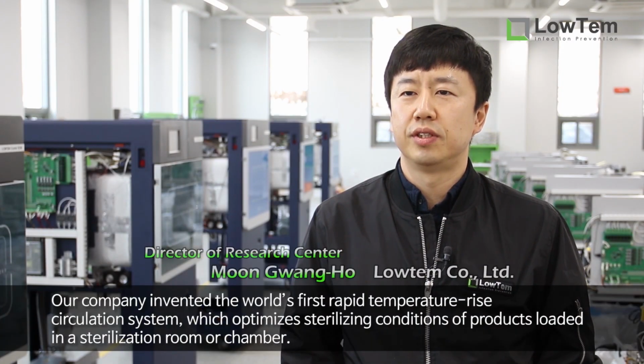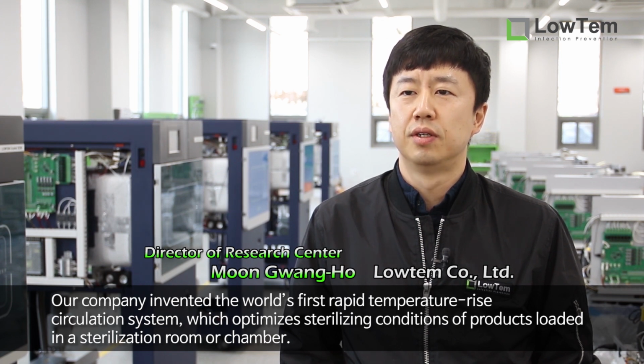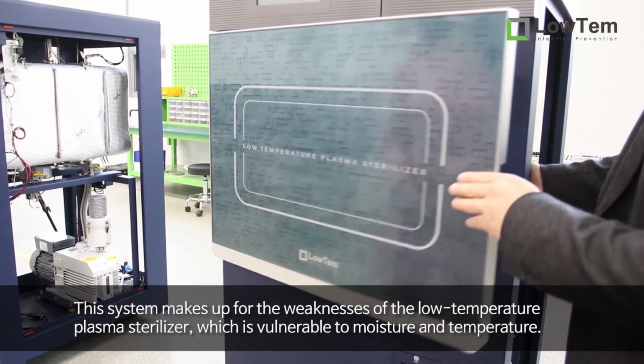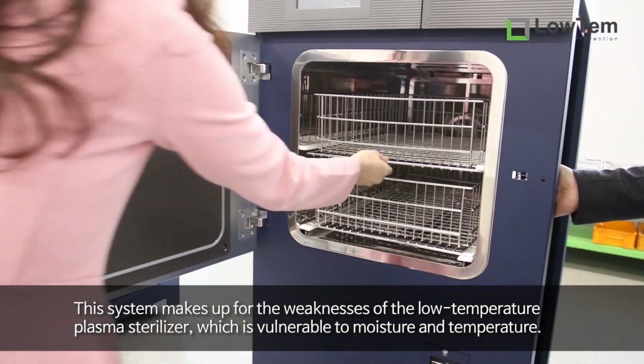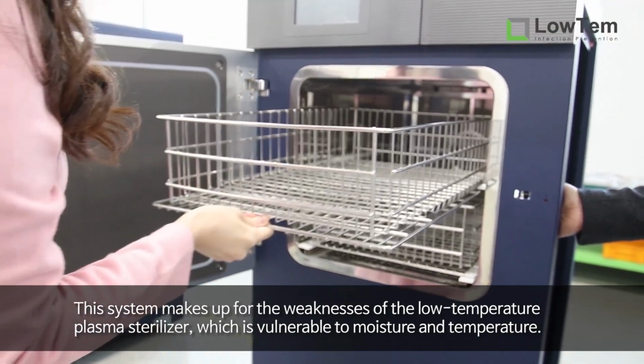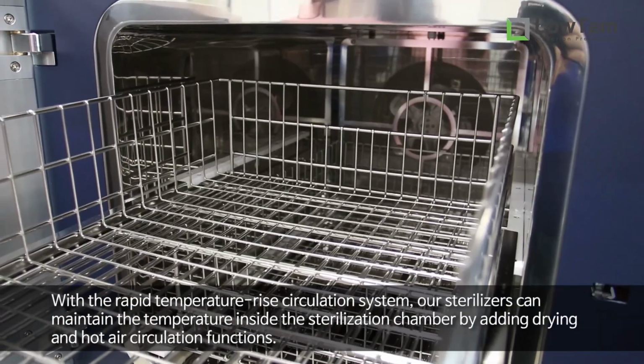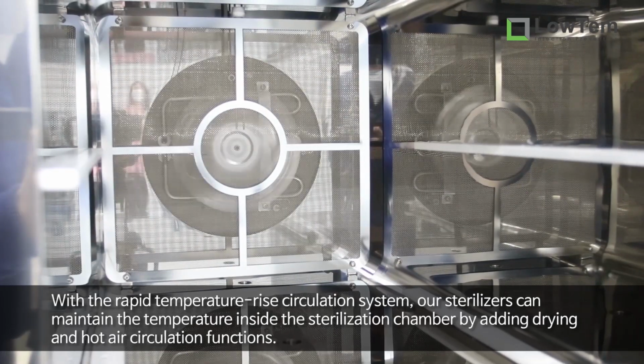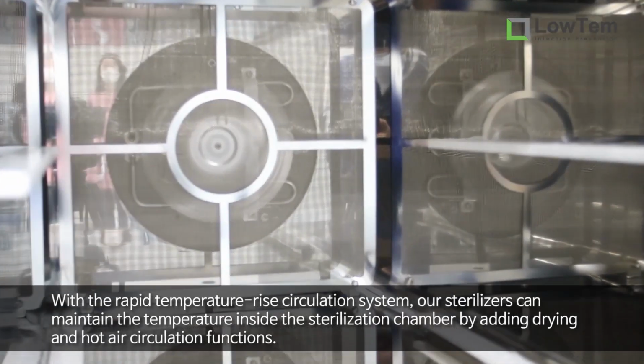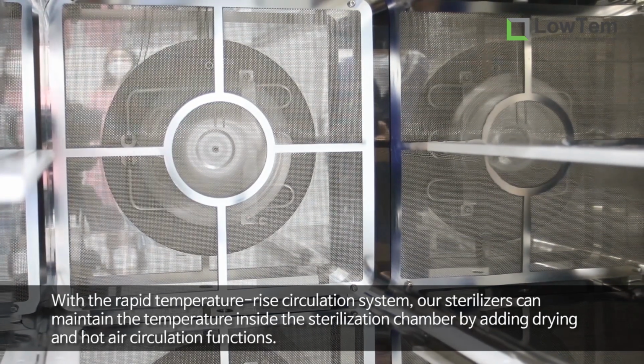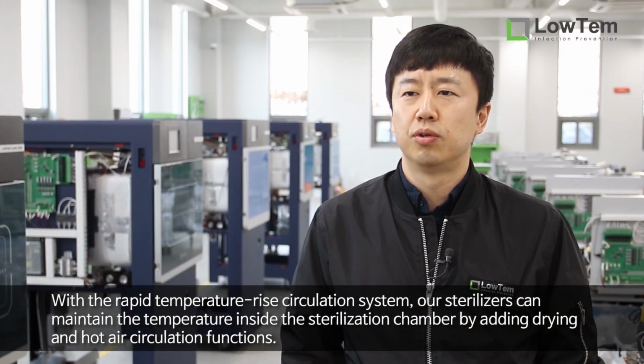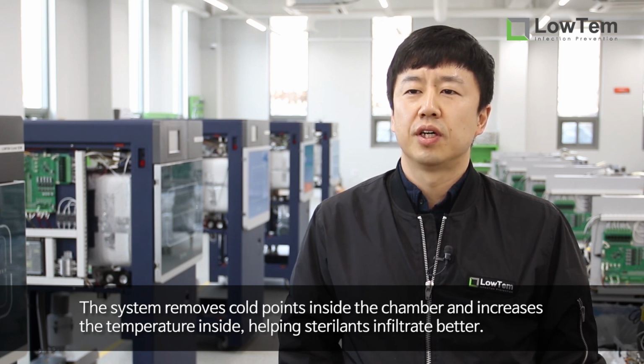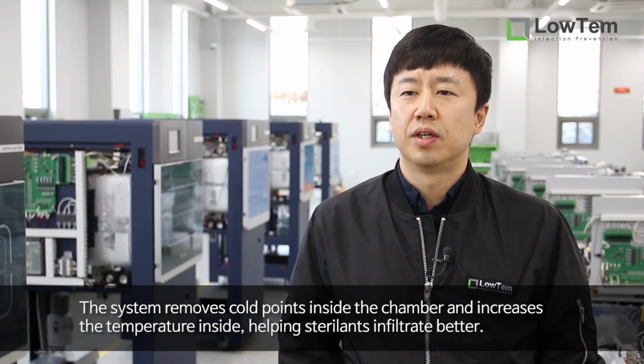Our company invented the world's first rapid temperature rise circulation system, which optimizes sterilizing conditions of products loaded in a sterilization room or chamber. This system makes up for the weaknesses of the low-temperature plasma sterilizer, which is vulnerable to moisture and temperature. With the rapid temperature rise circulation system, our sterilizers can maintain the temperature inside the sterilization chamber by adding drying and hot air circulation functions. The system removes cold points inside the chamber and increases the temperature inside, helping sterilants infiltrate better.